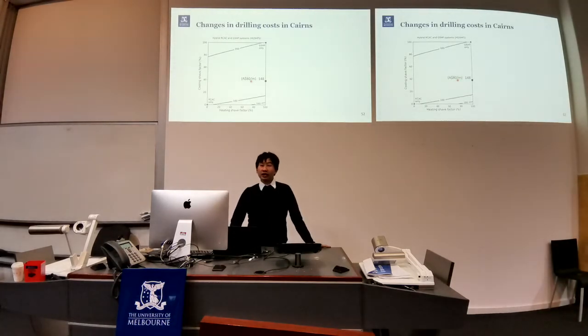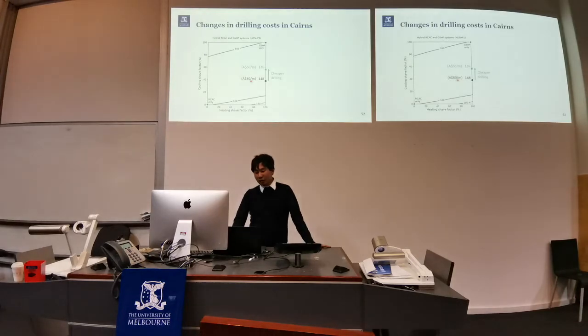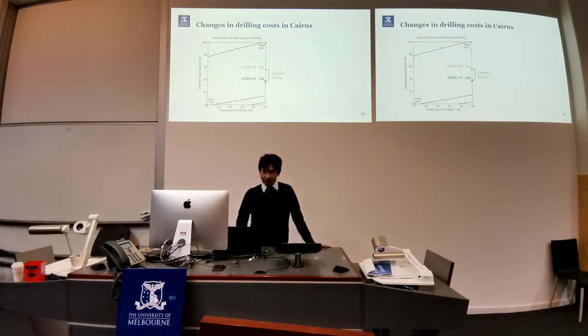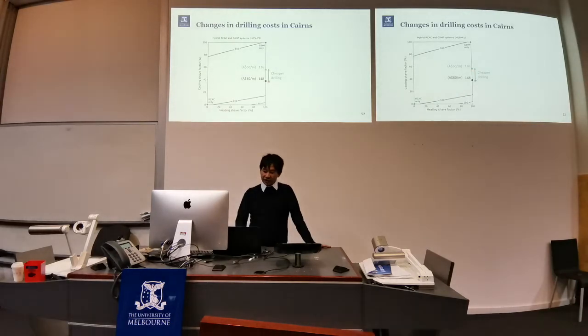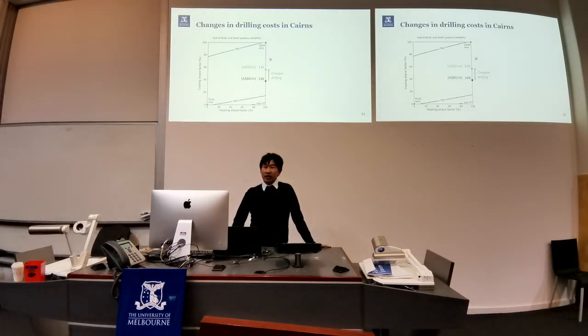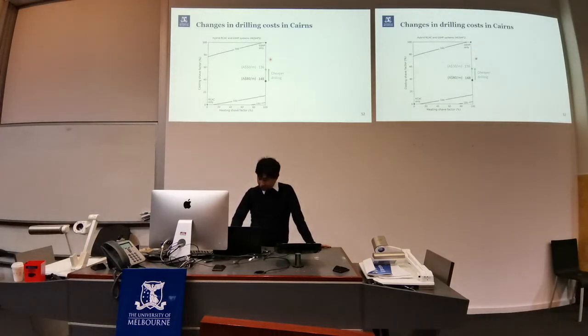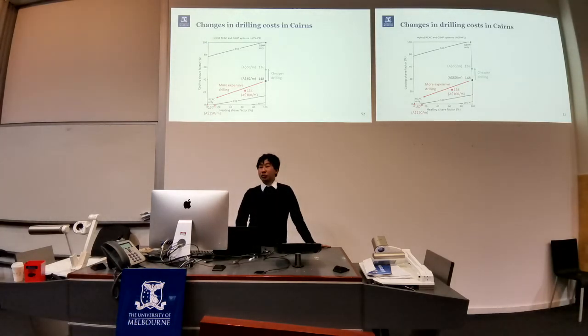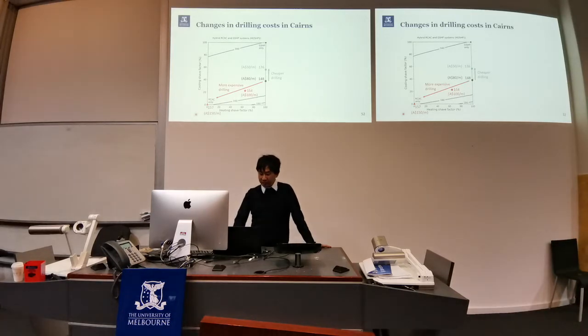The result from before was when the drilling cost is around $80 per meter. Now, imagine if this drilling cost gets cheaper to reflect a more competitive environment. As you can see here, with a lower drilling cost at $50 per meter, the lowest normalized cost decreases and the optimum point shifts towards the ground source heat pump system. It makes sense that in the cheaper drilling cost scenario, the ground source heat pump system would be more preferred. On the other hand, if the ground source heat pump system gets more expensive, then this lowest normalized cost will increase and the conventional system would be preferred instead. In fact, when the drilling gets too expensive, such as when the ground condition is very difficult, a more efficient ground source heat pump system is simply not viable at all, and your conventional system would be more financially preferred.